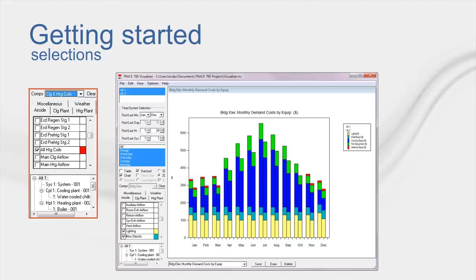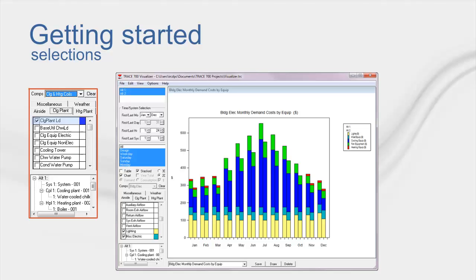One of the more common things that people select within this section is the cooling load checkbox, because Trace uses hourly time steps, which means it gives you the BTUH for every hour for the plant. So if you have a pre-existing load, you can compare it against one you've created in Trace, and then adjust the Trace load profile to match the one you have in real life.